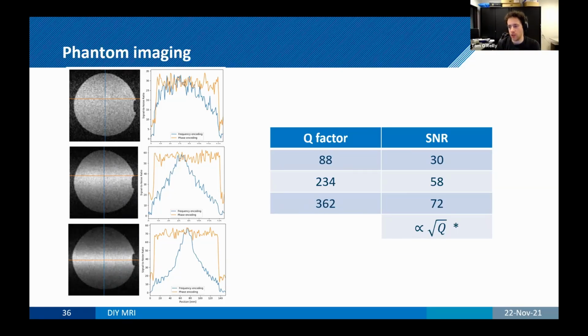So we're working on trying to get that to work at low field, because in principle, that should get rid of this frequency weighting, since you've destroyed your Q factor without adding losses. In that way, we should be able to get the SNR that we can get with these high quality factor coils, but without the frequency weighting. It's something we're looking at, but you can't buy a lot of these amplifiers for low field. So that's where we've been focusing on the development.